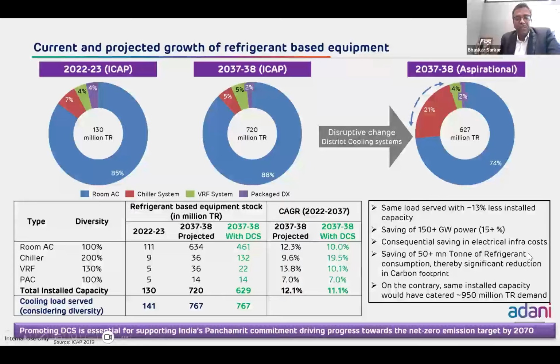So if this amount of growth is allowed to grow, then the load which is required, the installed capacity required to serve this would be 720 million TR by 37, 38 vis-a-vis 130 TR only, which was there at 22, 23. And this amount of TR would be required to meet the cooling load which is going to happen, which is 767 TR by 37, 38.